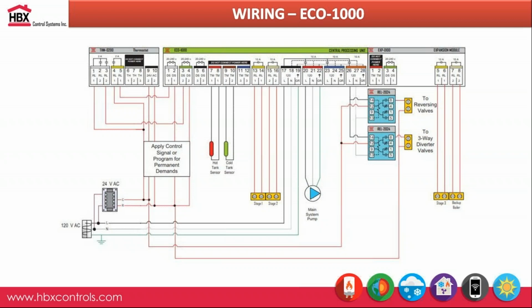In terms of your sensors, on pins 7 and 8, 9 and 10, this is where you would hook up a hot tank or cold tank. If you just put a sensor on pins 7 and 8, that's telling the controller that we're utilizing a single tank system. 11 and 12 is for if you want to do outdoor reset within the controller. 13, 14, 15, and 16 is where you would wire up your first and second stage of your heat pump. Then 120 just to power up the controller is on pins 17 to 19.